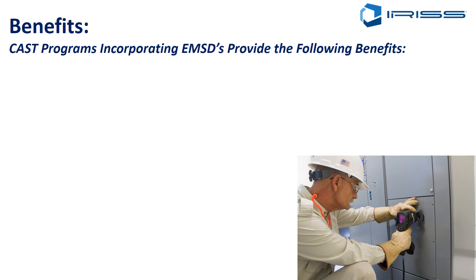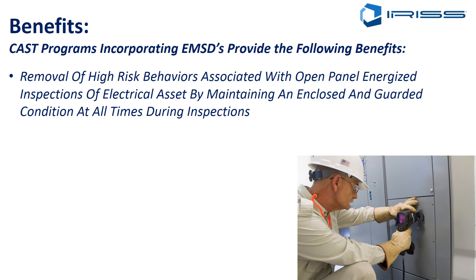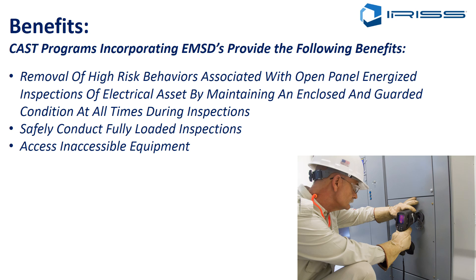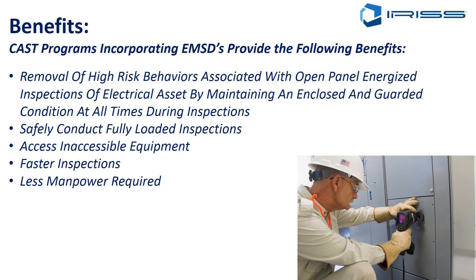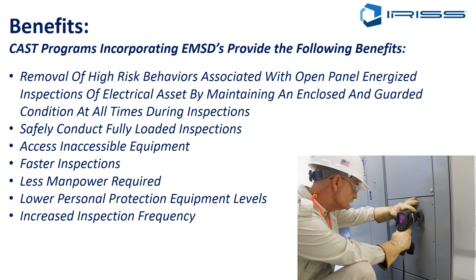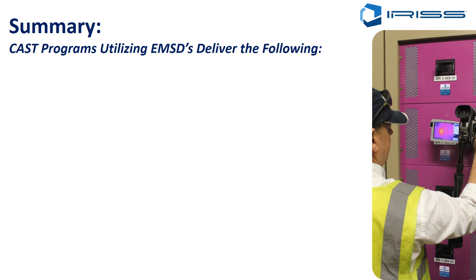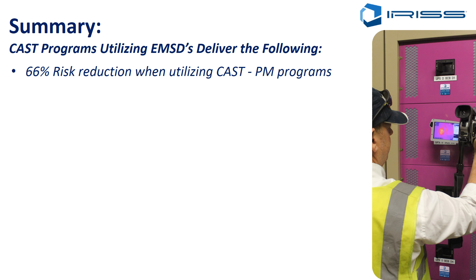CAST programs incorporating EMSDs provide the following benefits: we remove the high-risk behaviors associated with open-panel energized inspections of electrical assets by maintaining an enclosed and guarded condition at all times. We safely conduct fully loaded inspections, access previously inaccessible equipment, achieve much faster inspections with less manpower required since we're not removing panels, lower personal protective equipment levels because equipment is closed and guarded, and achieve an increased inspection frequency.